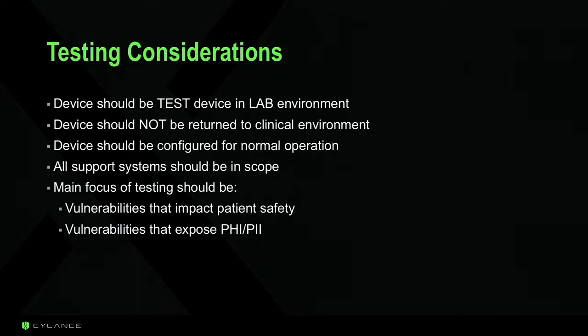All supporting systems should be in scope. The main focus of testing should be two things: first, anything that impacts patient safety — the integrity of data as it relates to patient safety or the availability of the device; and second, anything that exposes PHI or PII, which is a big concern under HIPAA. Patient safety is first priority, PHI/PII second, and anything else is tertiary.